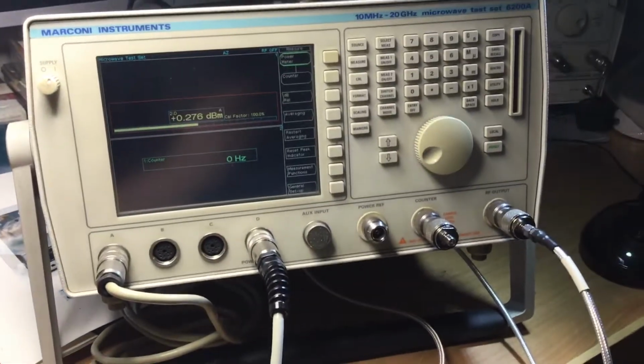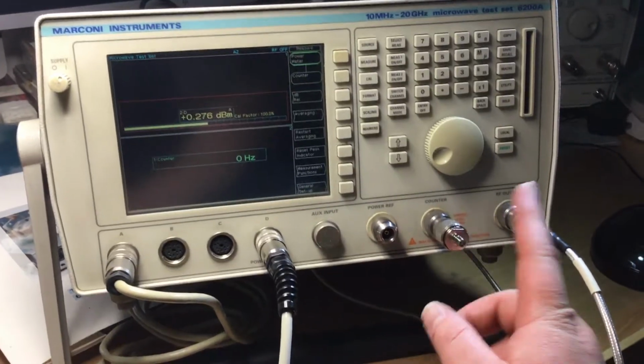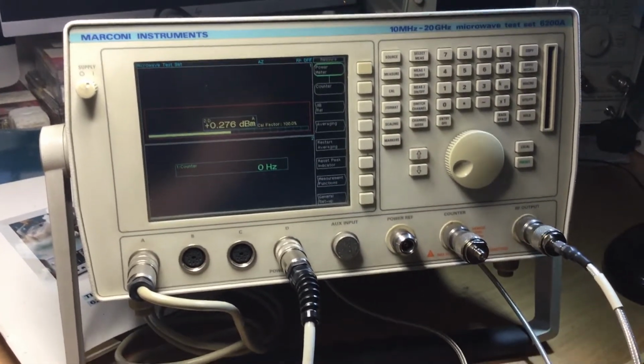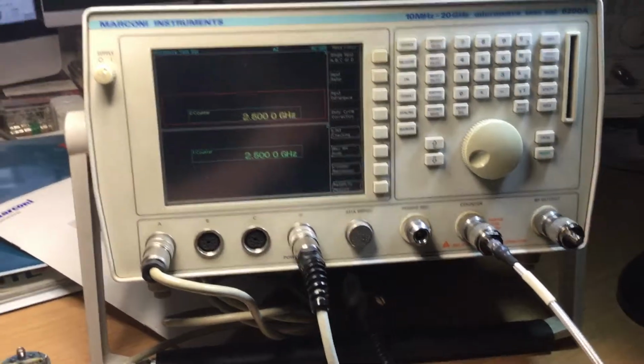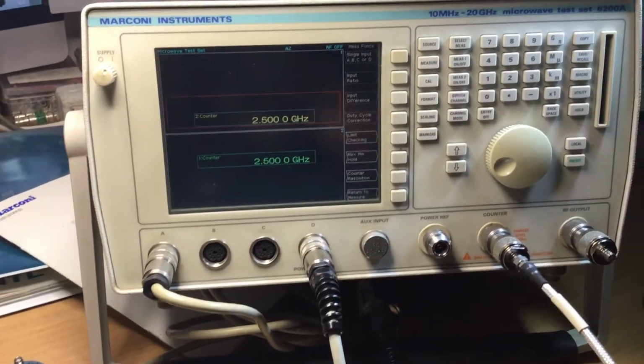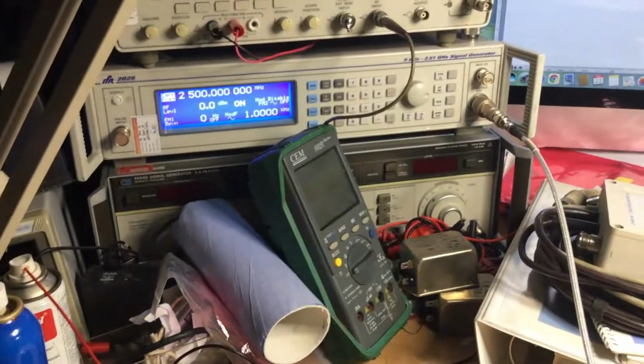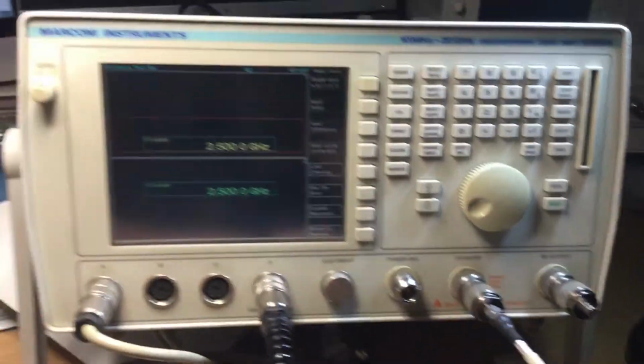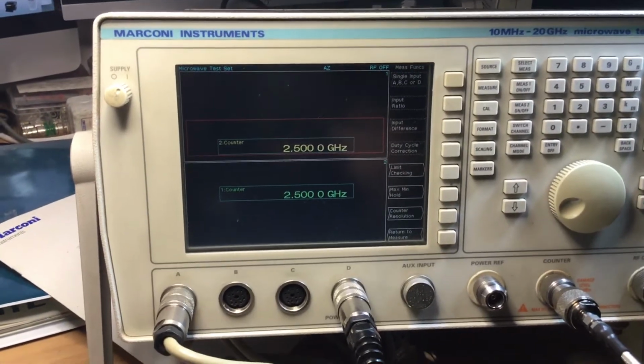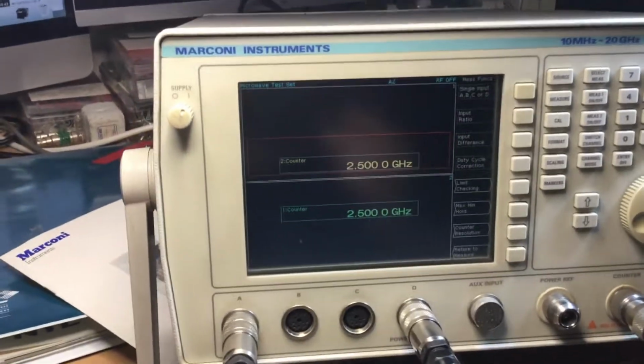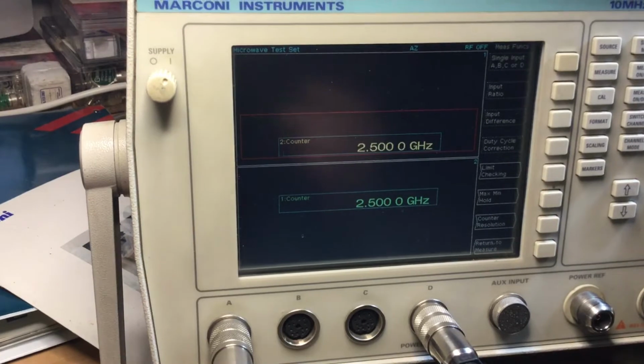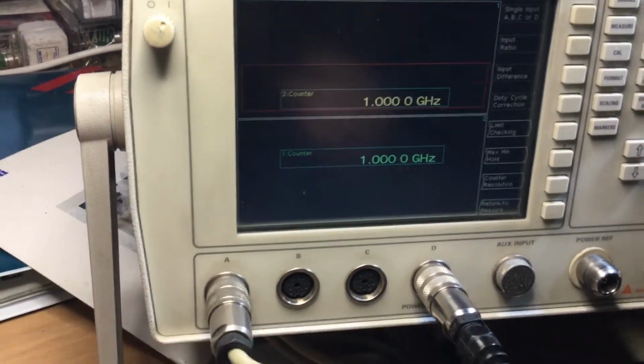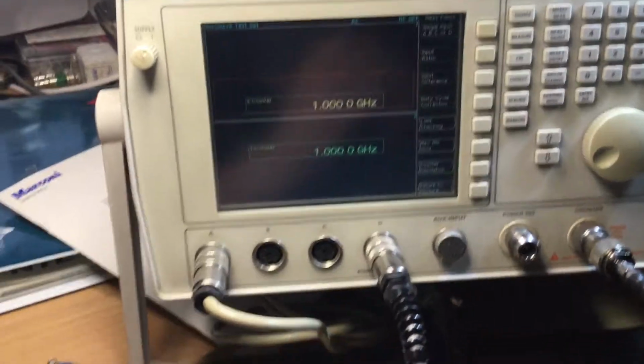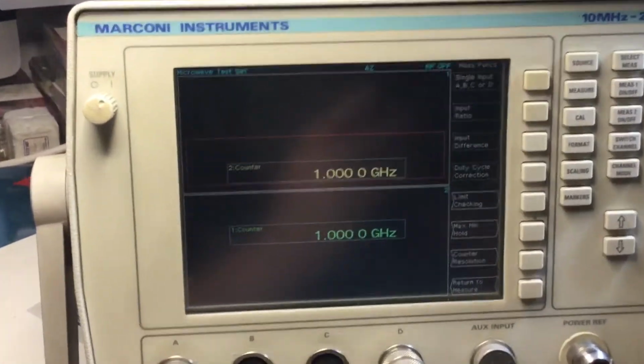We've got a frequency counter here. I'm just going to set up a measurement now where I can demonstrate the frequency counter, which is fed in on this input here. So please bear with me a second. Right, we've set up a frequency measurement for the frequency counter. We're generating a 2.5 GHz signal at 0 dBm into the frequency counter input, and then we've got a frequency reading there. Obviously, if I change that to, say, 1 GHz, naturally the counter moves with it. Now you can set up different resolutions on this as well.